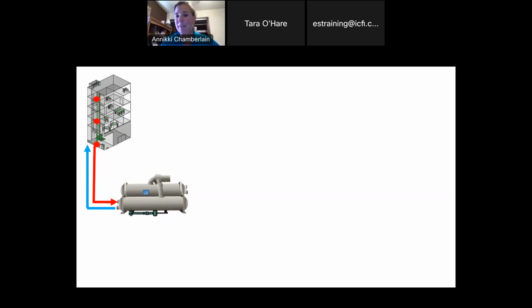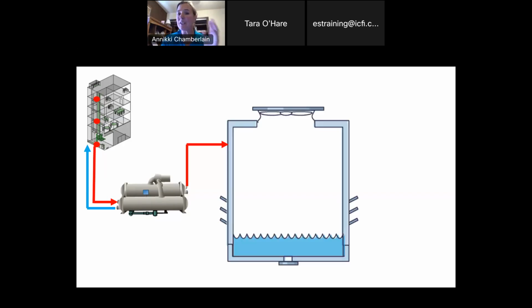Well, what magic happens inside the chiller? We won't talk about that, but that heat basically gets transferred. And now we're going to send that heat that we don't want in our building or our process into the cooling tower. Now, cooling towers, as we all know, are designed to evaporate water to create cooling. They're made to use water, so we don't want to restrict that. So we send that hot water, the water that's picked up that heat, into the cooling tower.